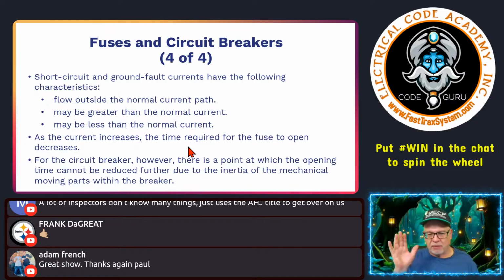And again, this takes care of itself, but it's just something that you know, that of the three things, you understand that short circuits and ground faults typically result in current potentially traveling on paths that they weren't intended, which is energizing metal parts in many cases. That's why we bond. That's why we do what we do. Okay, and that's why overcurrent protective devices have to be sized so importantly, and you don't overfuse stuff.